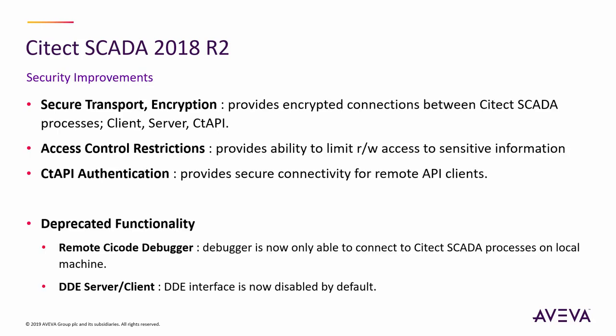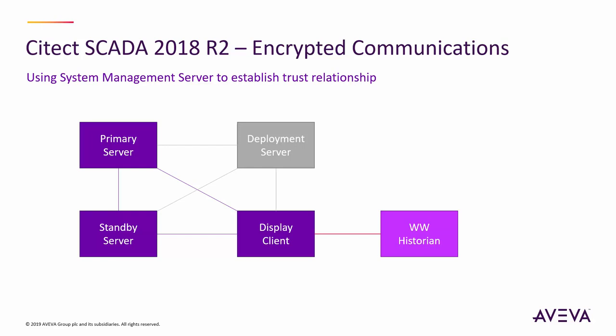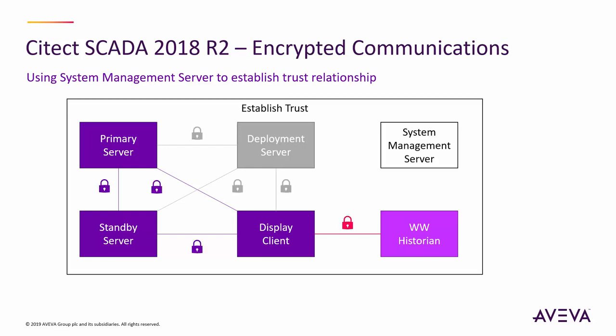There's also been a significant investment in security within the 2018 R2 release, adding support for encryption, user groups for access control, and more. In addition, some legacy functionality is now disabled by default. For example, a standard redundant configuration with a primary and secondary server pair, a remote client, a historian, and a deployment server can now easily be encrypted with the addition of a system management server. This facilitates the creation and deployment of certificates to establish a trust relationship between all system nodes.